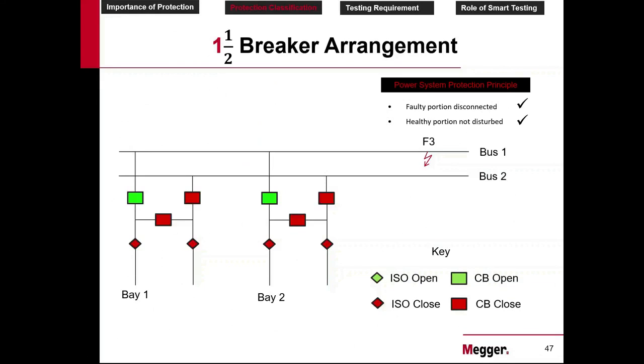It's an expensive solution because what you are seeing here is a single line diagram. In reality, this is RYB, RYB, RYB here. That means 9 breakers. So it's a very expensive system. So we have both the systems currently in use. For users who can wait for 40 minutes or 30 minutes, depending on the number of isolators in their system, they can go for the previous arrangement. So technically speaking, this is the best. But it's a very expensive solution.